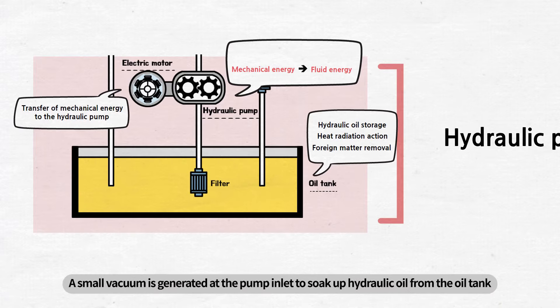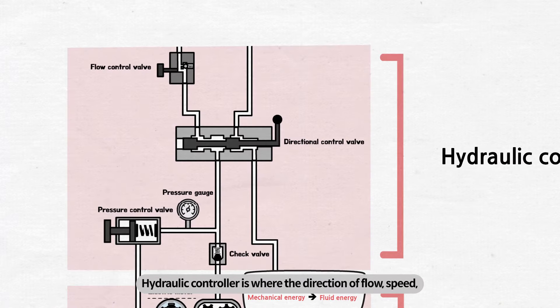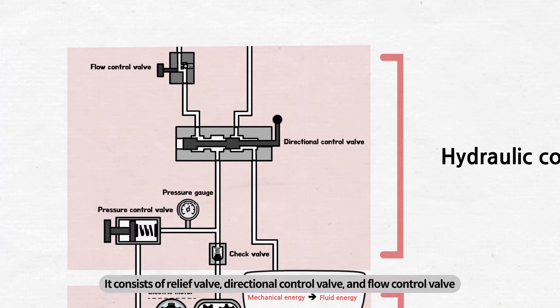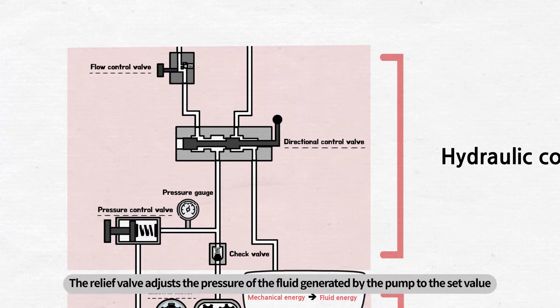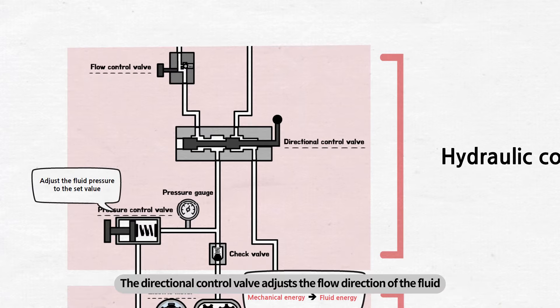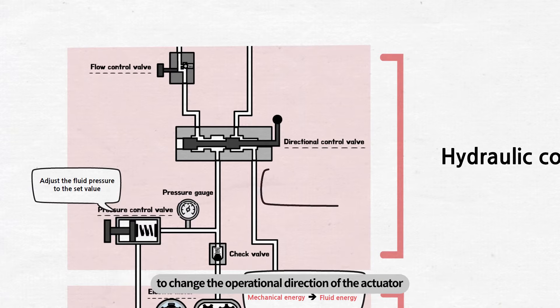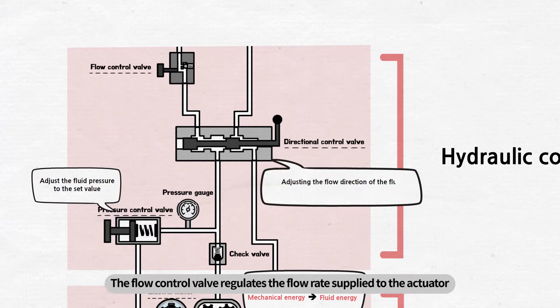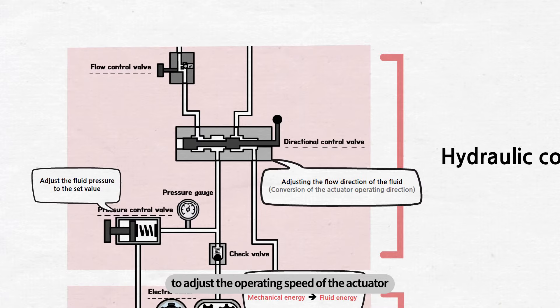Next is the hydraulic controller. The hydraulic controller is where the direction of flow, speed, and pressure of the high-pressure oil generated from the hydraulic generator is being controlled before it reaches the actuator. It consists of a relief valve, directional control valve, and flow control valve. The relief valve adjusts the pressure of the fluid generated by the pump to the set value. The directional control valve adjusts the flow direction of the fluid to change the operational direction of the actuator. The flow control valve regulates the flow rate supplied to the actuator to adjust its operating speed.